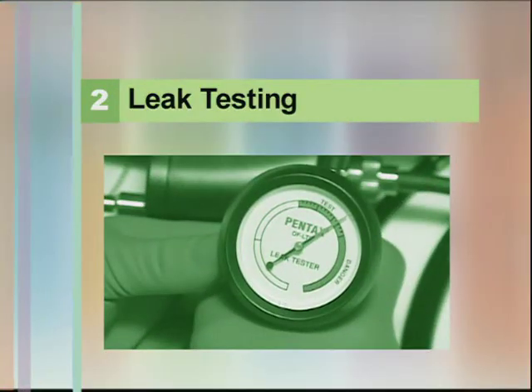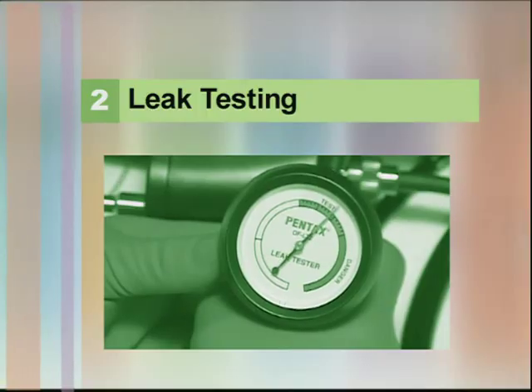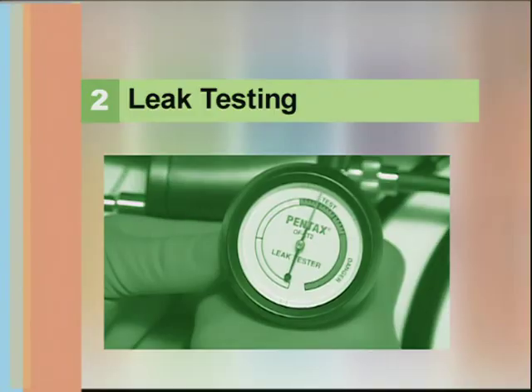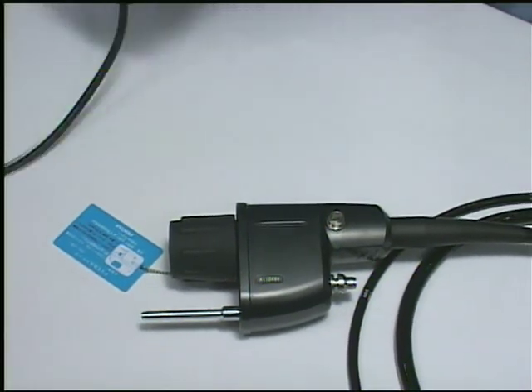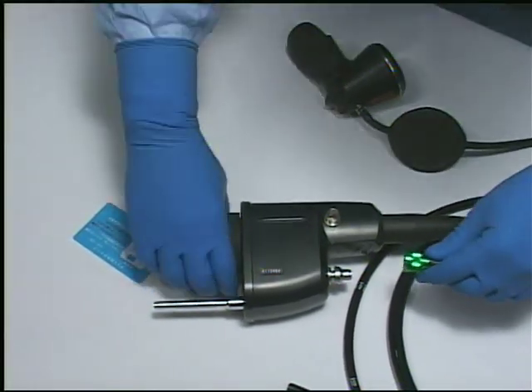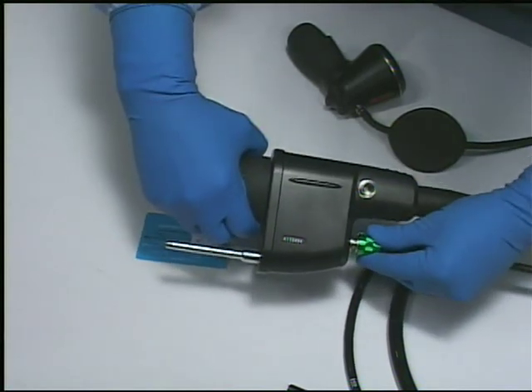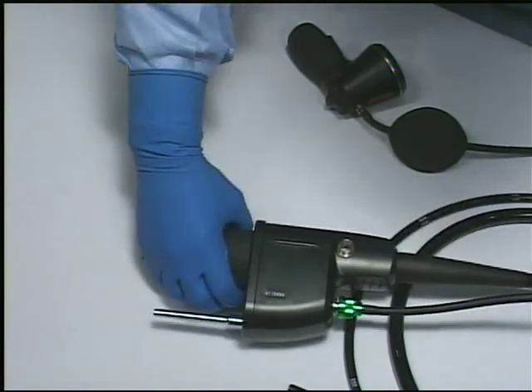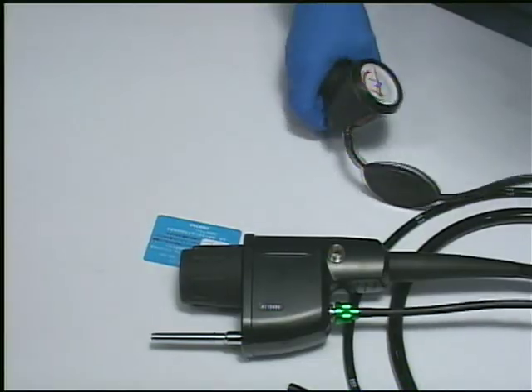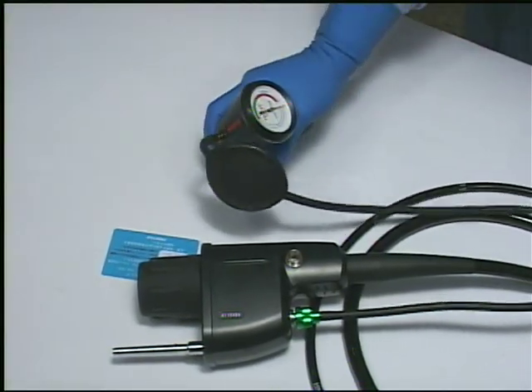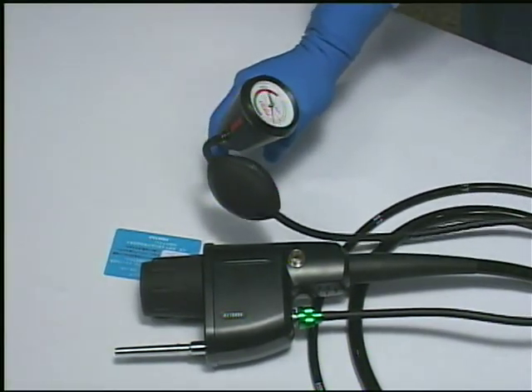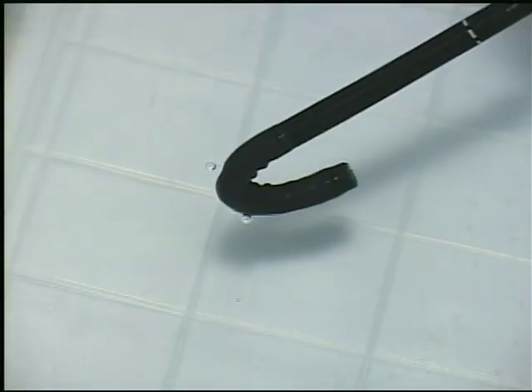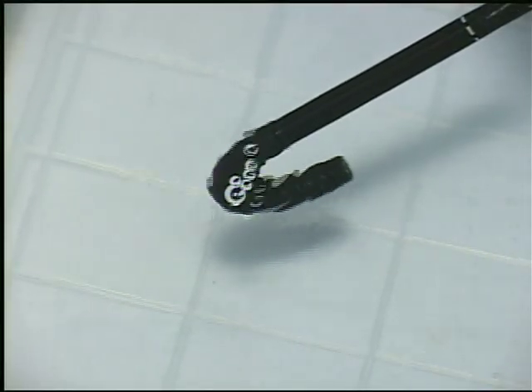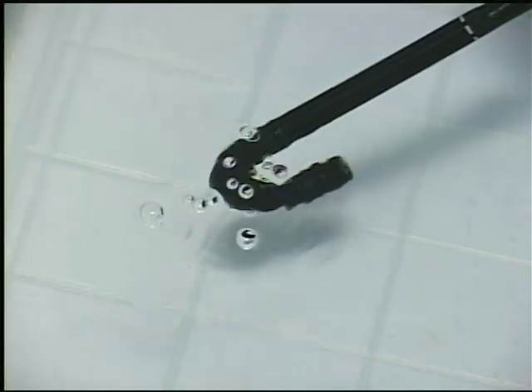Leak testing should be performed in a decontamination area prior to immersion of the endoscope in any cleaning detergent solutions. Leak testing goals: to identify any leaks or compromised areas of the endoscope which could potentially harbor microorganisms and act as a source of contamination if left unrectified. To confirm the watertight integrity of the instrument and to minimize the damage and repair costs associated with leaks.